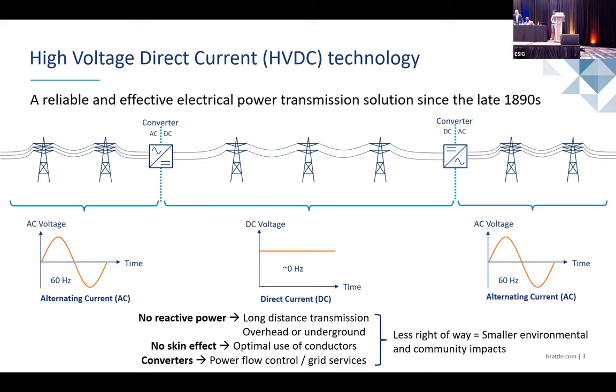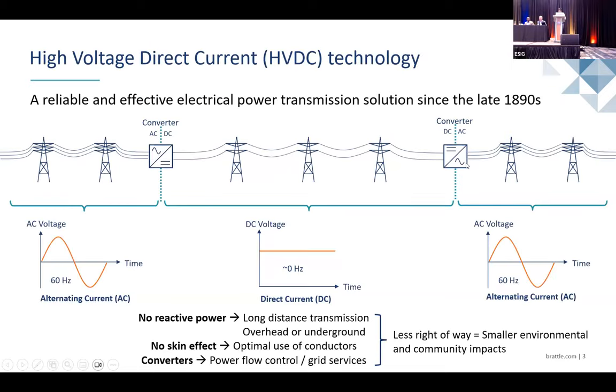As you see on the slide screens, HVDC is basically high voltage direct current technology. And it's traditionally been used to transmit power over long distance. This is the main purpose: in the initial days when the technology was invented, the purpose was to optimize the losses when you transmit over a long distance. As you see on the screens, in HVDC you have three major components. The first one is the rectifier, where you convert AC into DC, and then you put the DC power onto the DC lines. And then you send this power over a long line, and when it reaches the destination, you convert DC back into AC. And then you dump it into the AC grid.